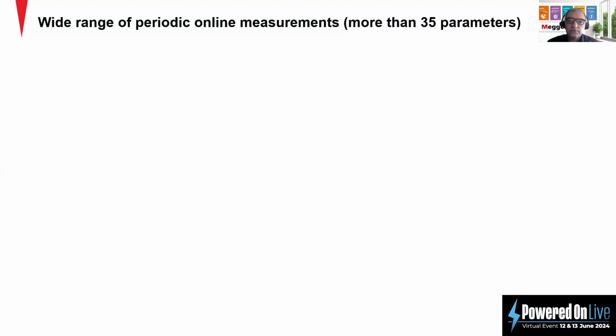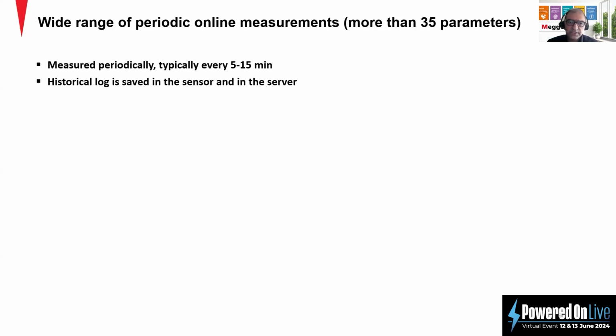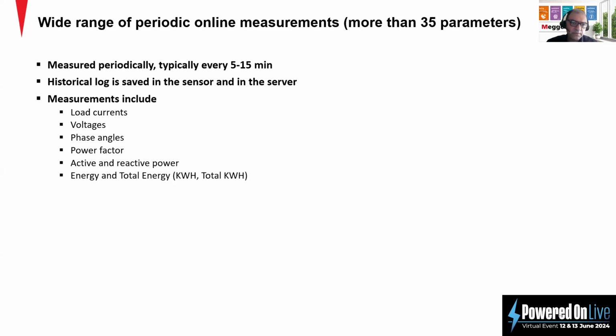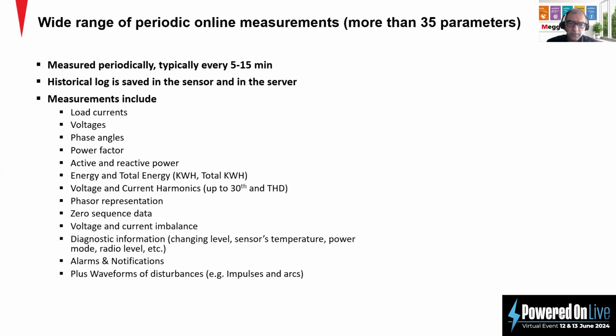Sensors perform measurements continuously, every 5 to 15 minutes according to the customer request, measuring more than 35 parameters from the network, and each parameter is saved on the sensor and the server. These measurements include load current, voltage, phase angle, power factor, active and reactive power, energy and total energy, voltage and current harmonics up to the 30th, total harmonic distortion, phasor representation, zero sequence data, voltage and current imbalance, diagnostic information for the sensor itself and the area around it, some alarms and notifications, plus waveforms of disturbances like impulses and arcs.